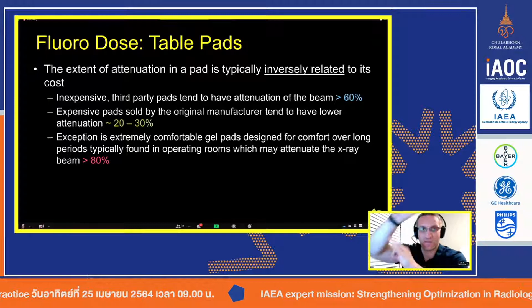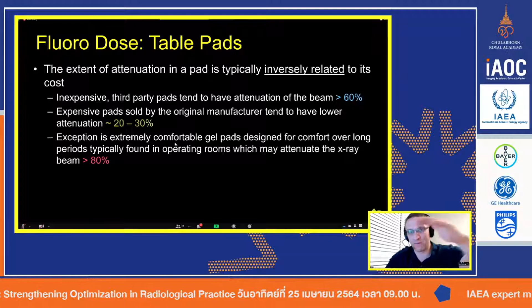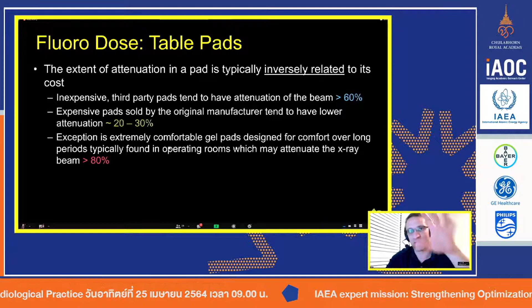Usually the pads sold by the manufacturers tend to be the lowest attenuating pads available. It's just because they've been created or engineered for fluoroscopic procedures. The worst pads out there, and this is something we can't really control, are usually the comfort pads that are in the actual patient beds. So if you're doing a C-arm in maybe the ER, or if they're up on the floor and you took a portable C-arm in to do a procedure, and they're in just a standard hospital bed, those pads can actually attenuate quite a bit of radiation.